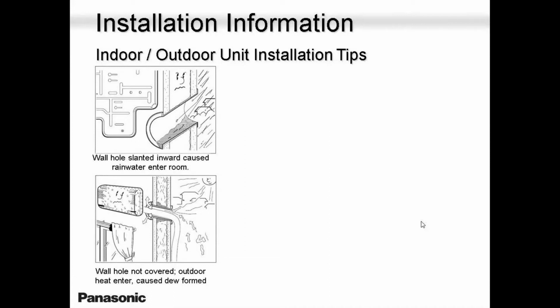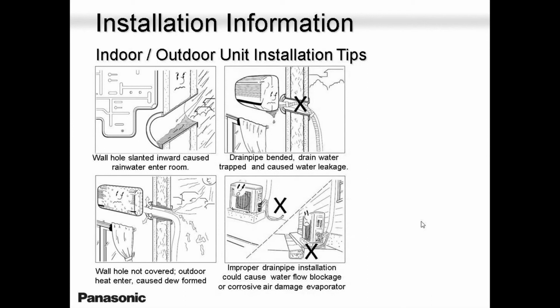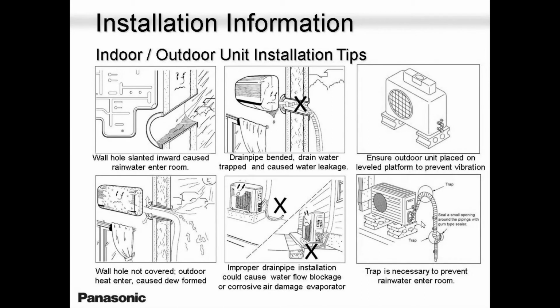Make sure I put enough screws, because if you don't fix this backplate correctly, after 6-7 months you will get a call complaining about the motor being noisy, because when you hung that unit it was not balanced. And in the long run, the blower wheel was going off the square, and eventually the motor conked off. So you will replace that motor. After another 6-7 months, you'll be called again. And I have seen that. So please, the backplate, I know it's something very simple, but it can cause a lot of problems.